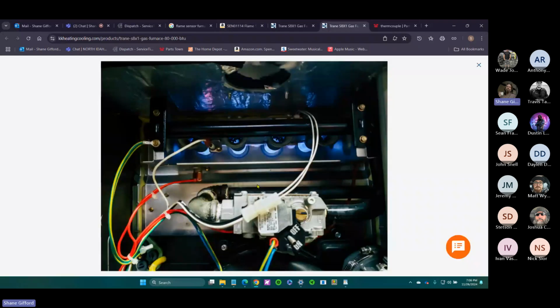But back to what Josh said. What's going to happen is we're going to get our call for heat. Doesn't matter if it's grandma's furnace or a gas pack, we're getting a call for heat. Some furnaces have an inducer motor. Some furnaces don't. Some of them are just natural draft. And when you have natural draft, you're pretty much just a gas valve and a thermostat, and that's it. There's no flame rectification. Your system is acting basically like a barbecue grill.